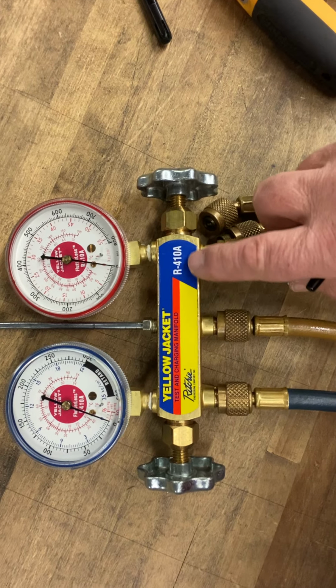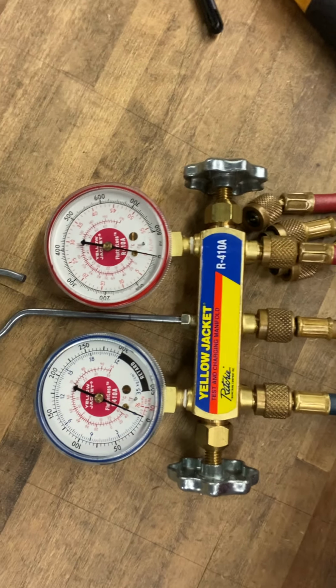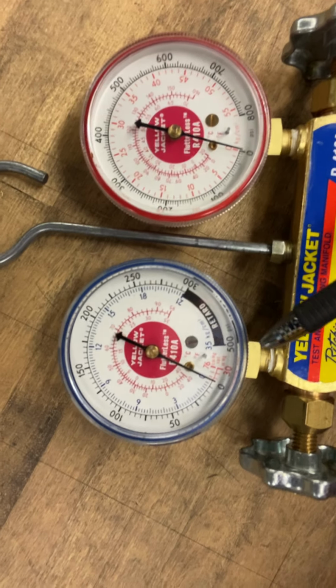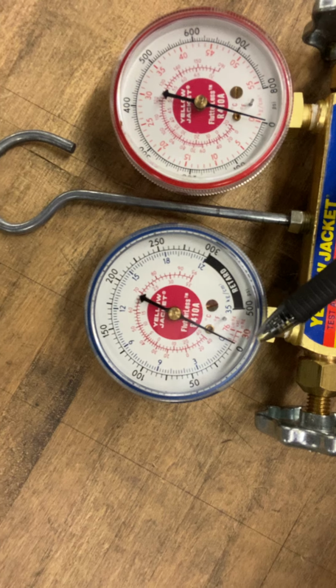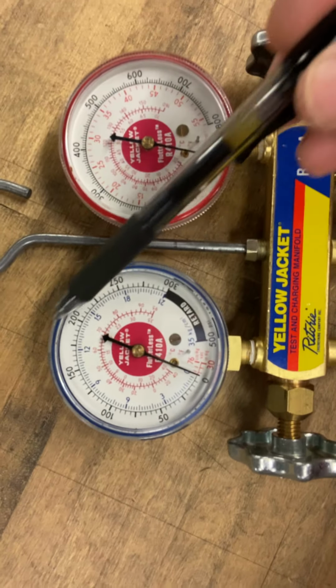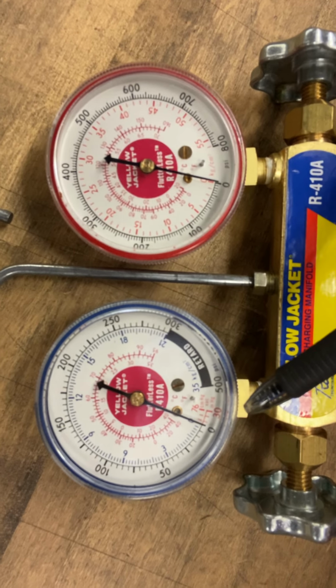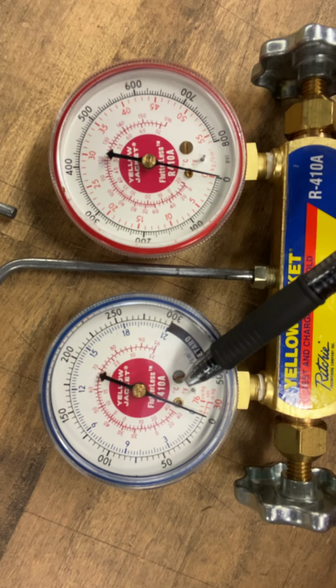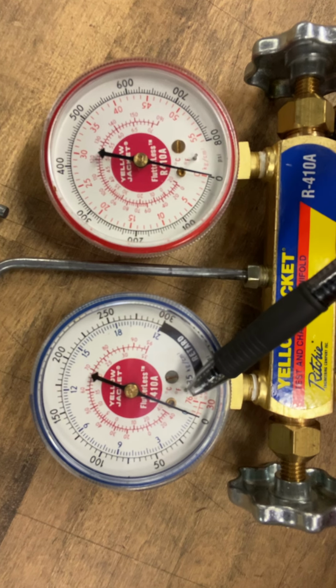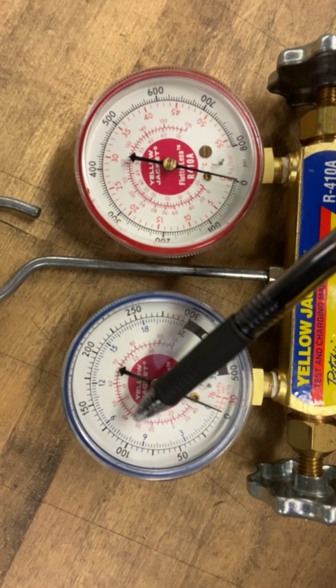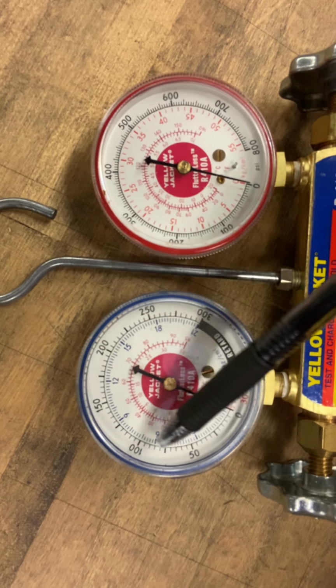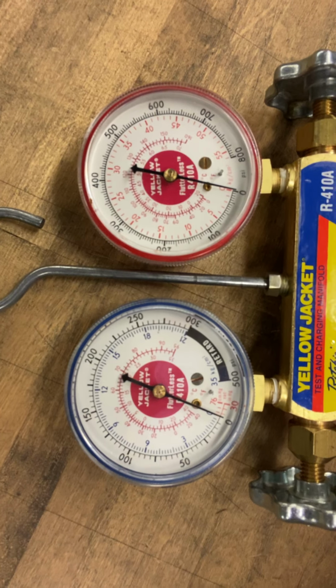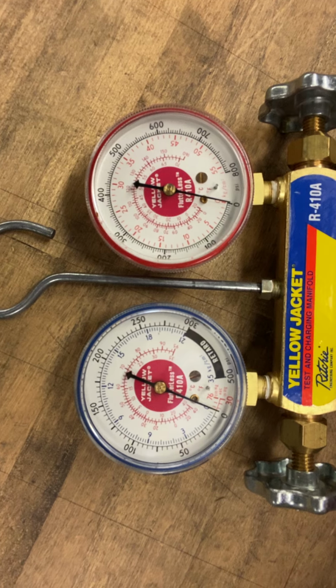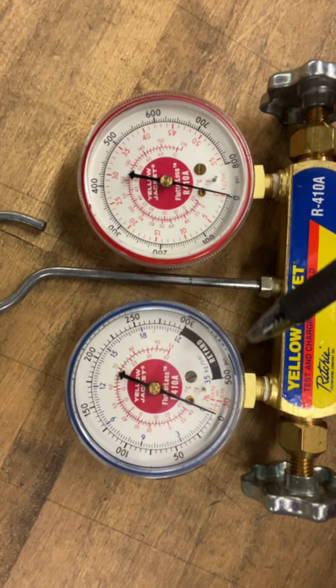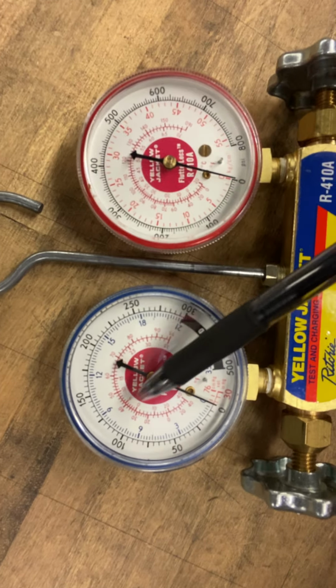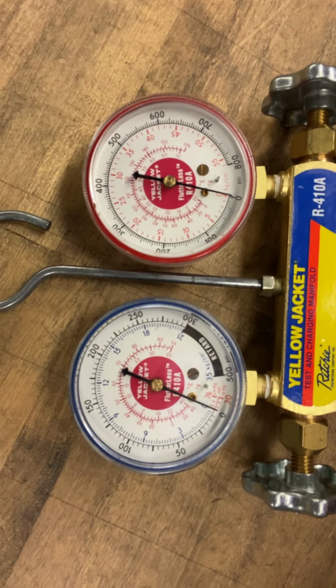This happens to be a dedicated 410A set of gauges, which only means that it only has a pressure ring for 410A. We have pressure on the outside, like we do on the other, and then the Celsius temperature for 410A and the Fahrenheit temperature for 410A, which is right there. It does have this other set of numbers, and I believe that's like international measurements - I don't use those. So that's kind of what this is.